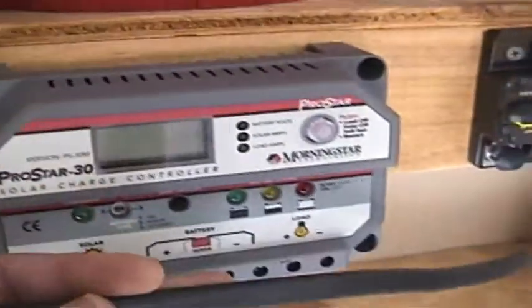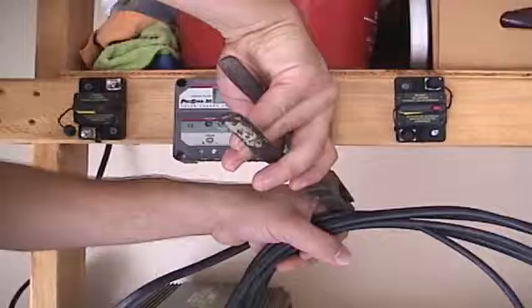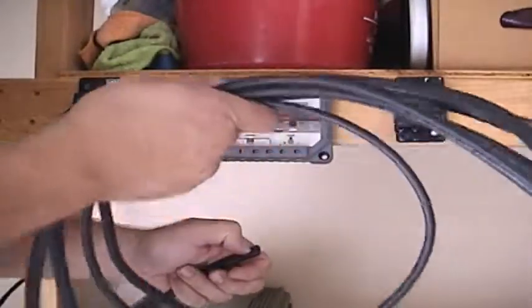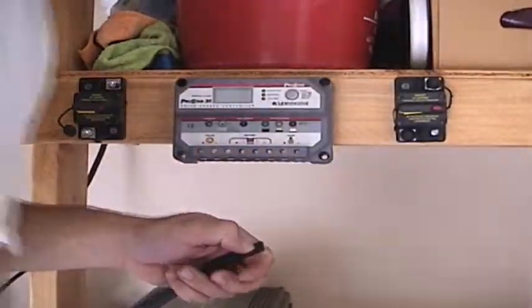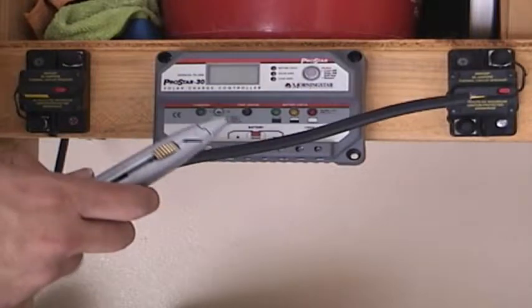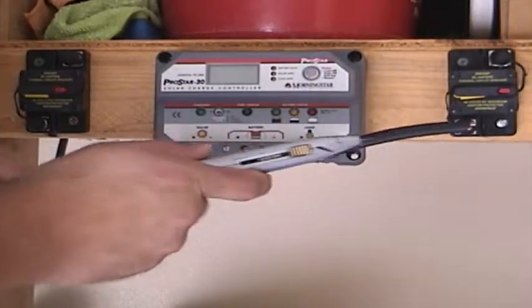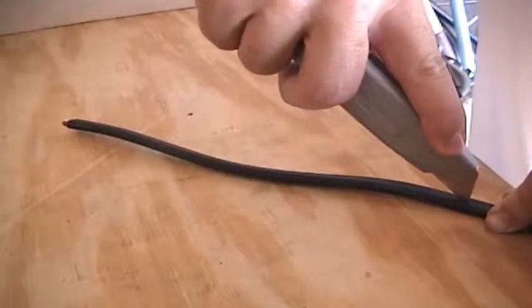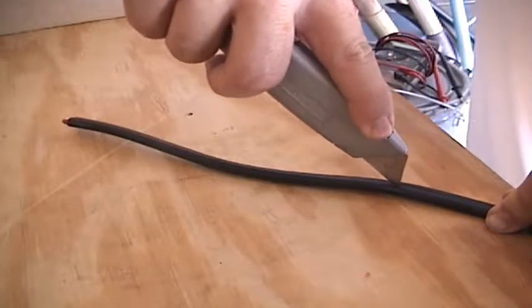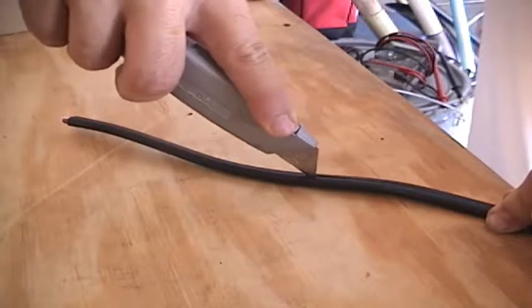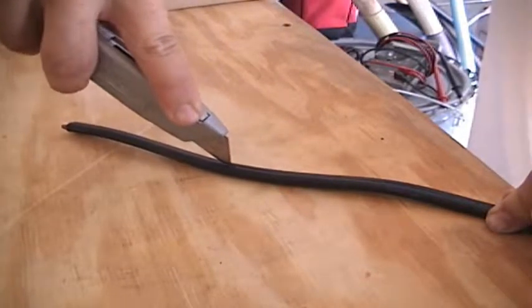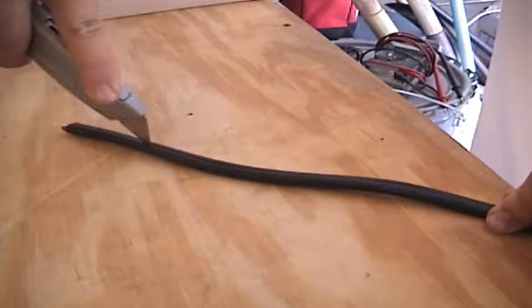Now let's grab the 10 gauge outdoor cable that we ran from the solar panels outside into the attic, down into the garage, and let's go ahead and cut it right at the solar charge controller. Once we've cut off the excess cable, let's set it aside for the moment. Then, taking our utility knife, we're going to cut off about 10 inches of the outer skin. Again, be careful not to cut through to the two 10 gauge conductors that are beneath the outer skin.